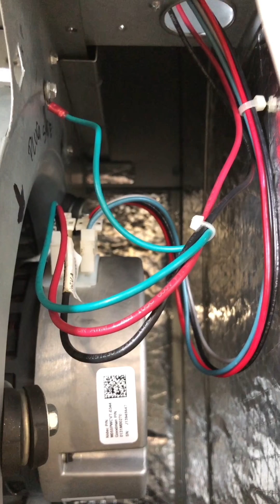Most blower motors inside these furnaces are going to have a capacitor. I'm not going to take that guy out, but you can see the top of it there. Just like the one over here that we talked about in the air conditioner. It's the same thing, it's just running the blower motor inside here. Let's go back over here to the electric furnace. This one actually doesn't have one because this is an ECM motor. And we won't get into that now, but it doesn't need a capacitor.